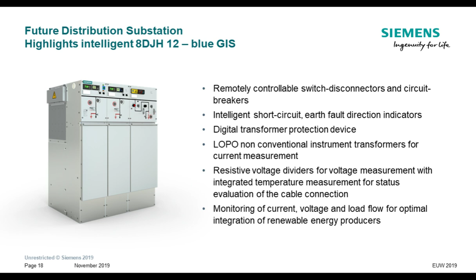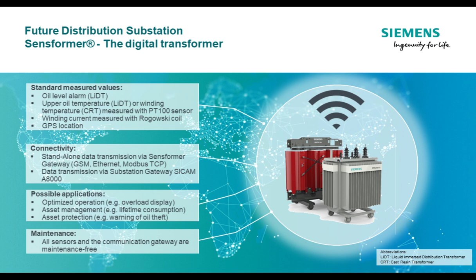Having a look at the other components installed in the future distribution substation, next to our ring main unit we also have a new digital distribution transformer, the so-called Sensformer. Sensformer is a distribution transformer, and together with its integrated sensors for oil level alarm, temperatures, and also for currents, it provides the value proposition to optimize the operation in overload situations, as well as asset protection and asset management. All the installed sensors in this Sensformer distribution transformer are connected to a centralized gateway, which is also part of this future distribution substation and which will be explained a little bit more in detail by Oliver.